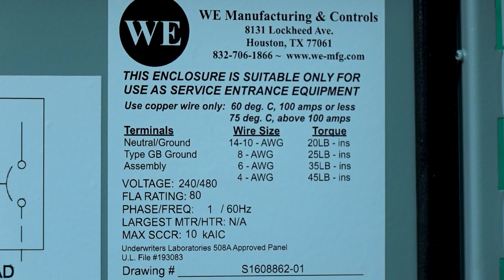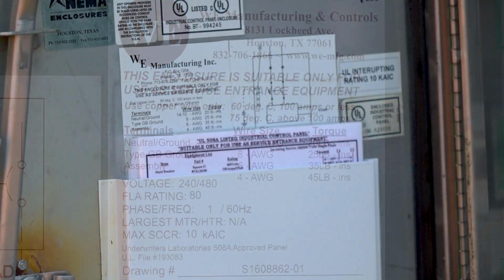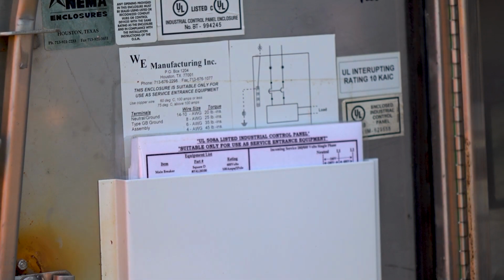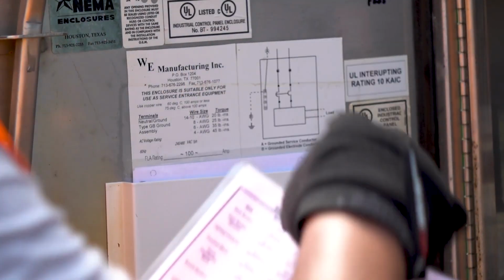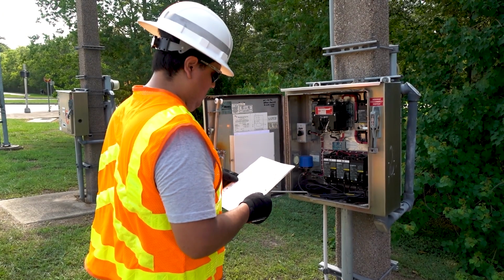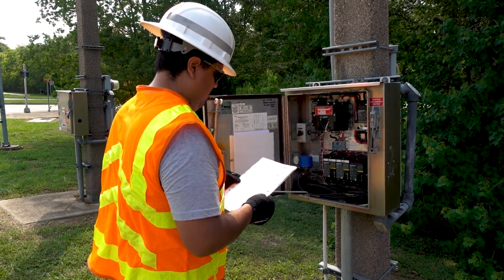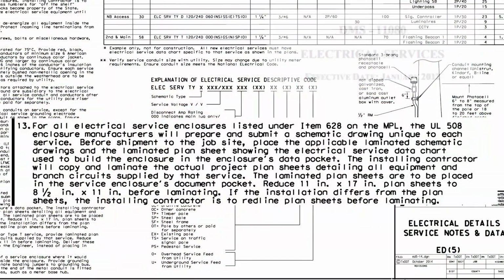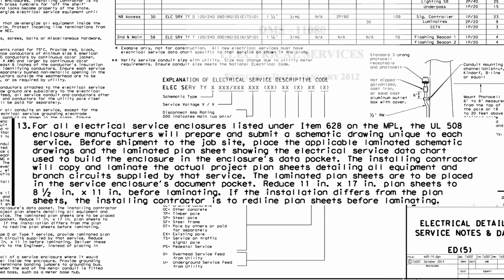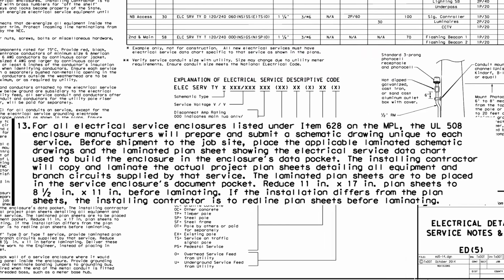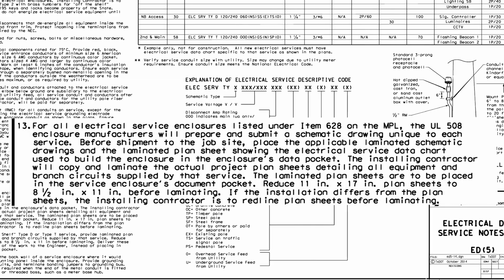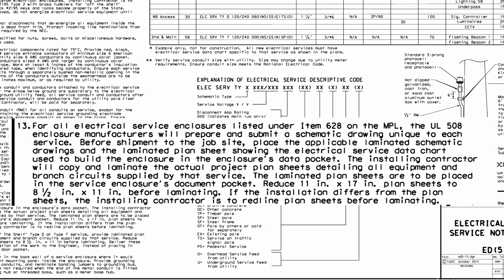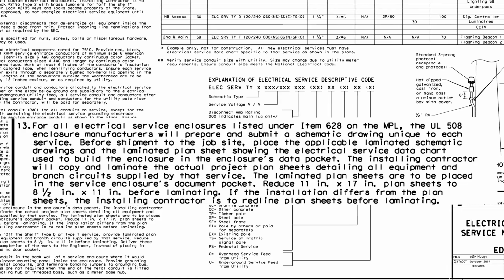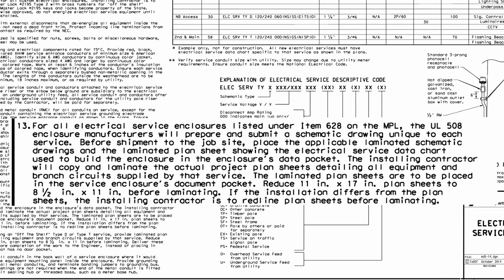There will also be a label in the same area of the electrical service enclosure that says, "Suitable only for use as service equipment." DMS 11080 6A Note 4: Enclosure requires a document pocket with minimum dimensions of 10 by 11.5 inches to be attached to the inside of the door. Standard sheet ED5 and DMS 11080 require the UL 508A service manufacturer to print and laminate a schematic drawing unique to each service. Before shipment to the job site, the laminated schematic drawings will be placed in the document pocket.